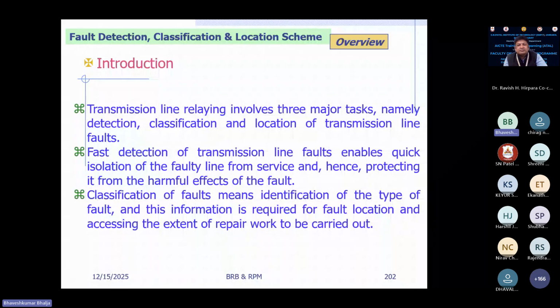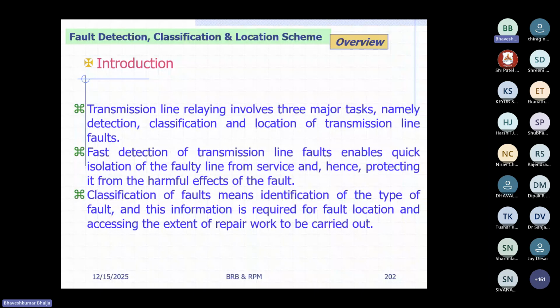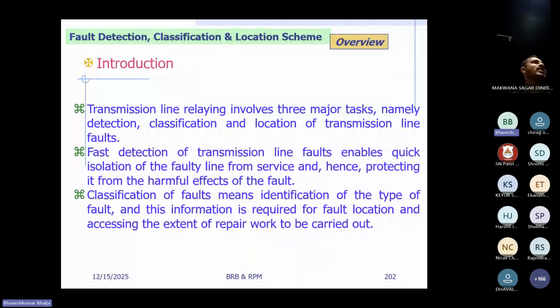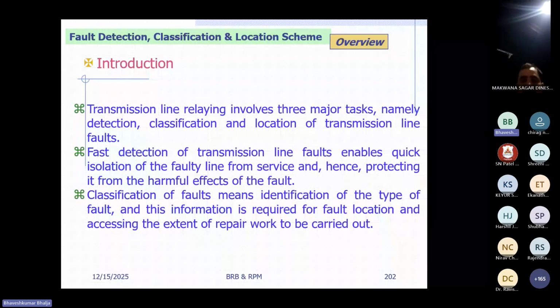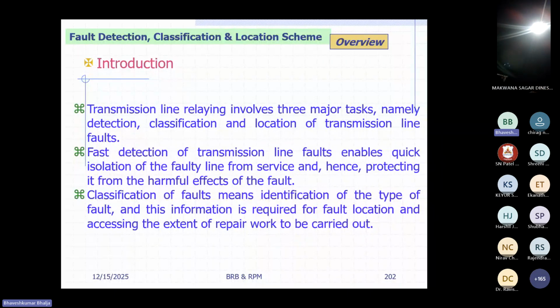And once you have isolated the faulty section, then you have to classify the faults. That means which type of fault it is: R to ground, Y to ground, B to ground, R-Y, Y-B, B-R, or RYG, YBG, BRG, RYB, or RYBG. So you need to identify which type of fault there is. Now, why is this important? Because the engineer working in the utility has to send the lineman for the maintenance work, the repair work.